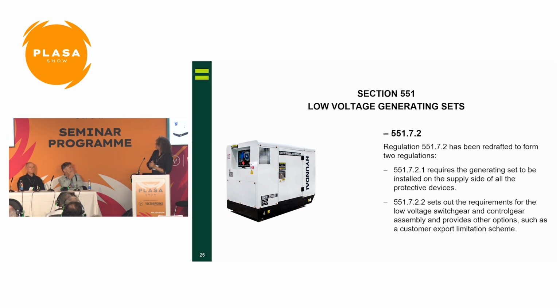Also, what's come along is that where you've got more than one source of supply and you're bringing that second supply into a distribution circuit, currently under BS 7671 it's permitted to have other loads on that circuit. What's being said here is the proposal that we should not have any other loads on that circuit. We should just have that dedicated source on that distribution circuit.